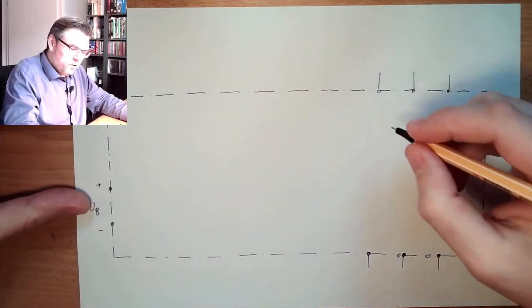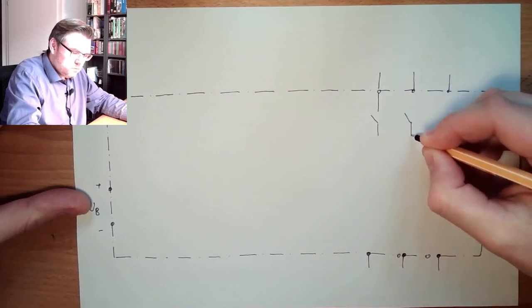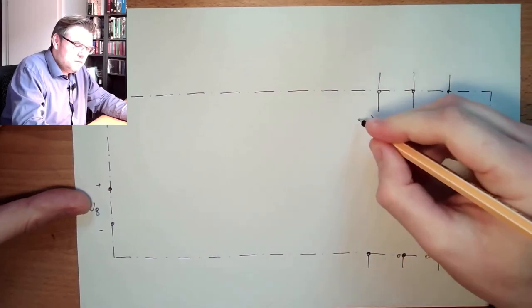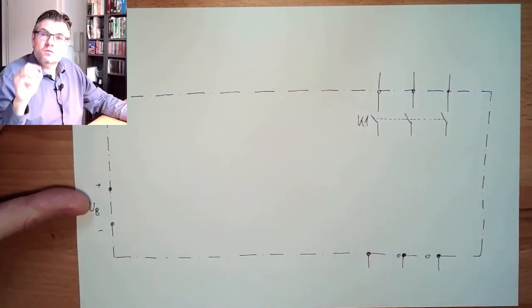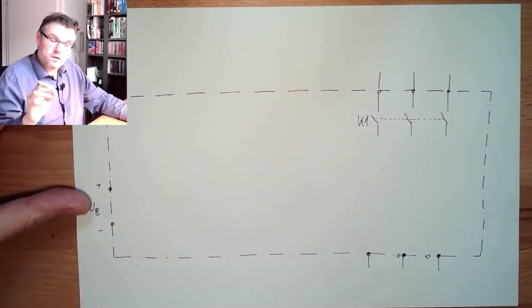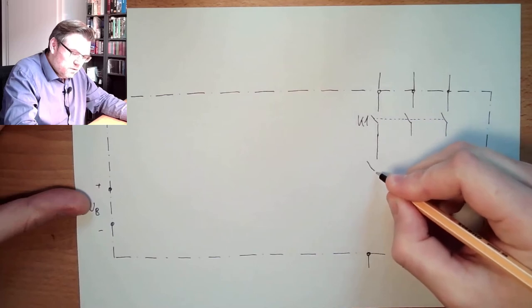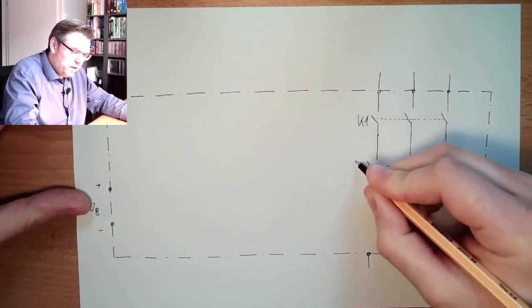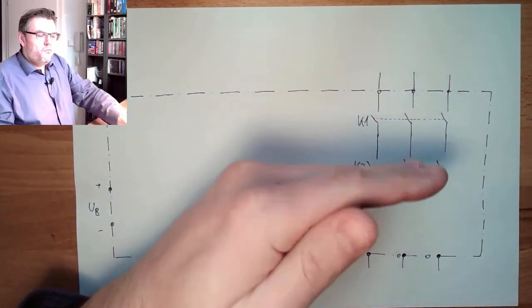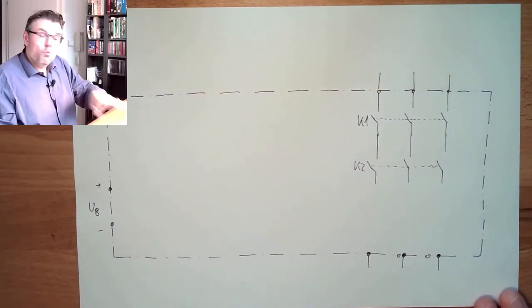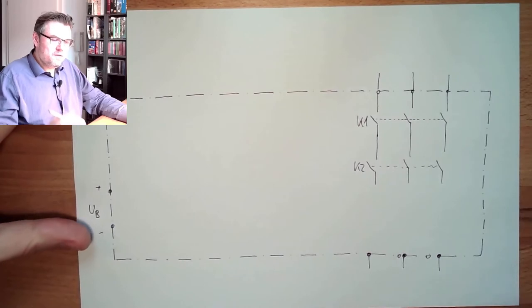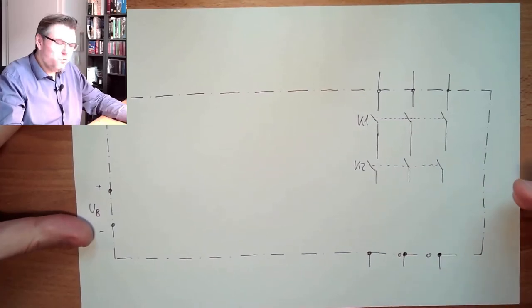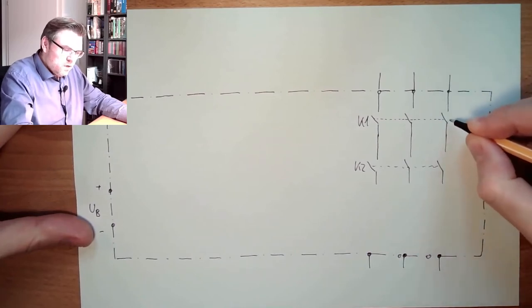So of course there is a switch inside, one switch. This is usually a contactor, and those are switched together. This is a contactor one, K1. And if I want to be safely switched off, I usually make simply a second contactor inside, second contactor K2, also connected to each other. So if one of those two contactors are opening, I switch off. One can already fail. This is actually the ground rule of safety: to do it twice, and only if those two are doing the same thing, it's safe.